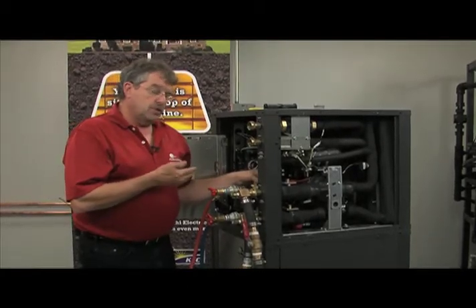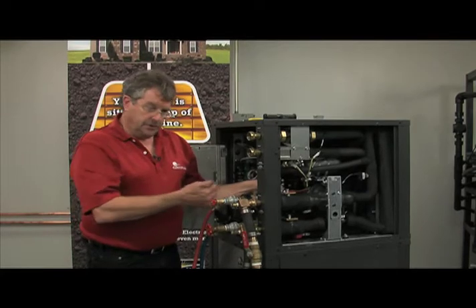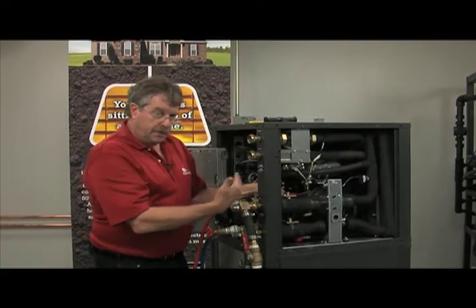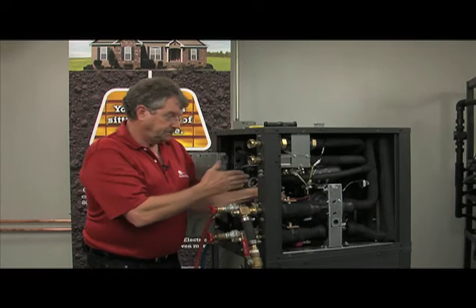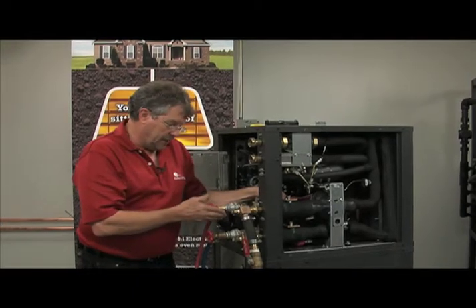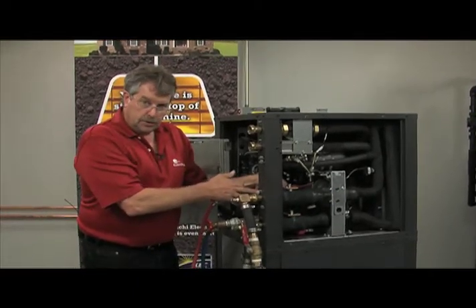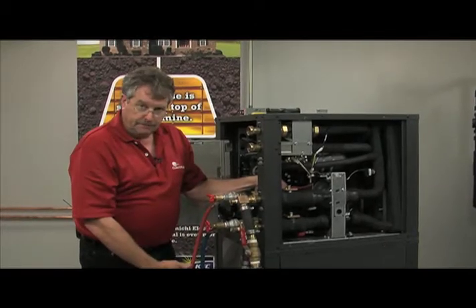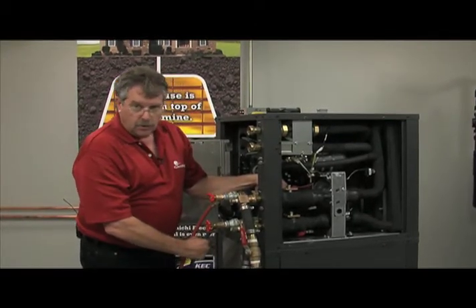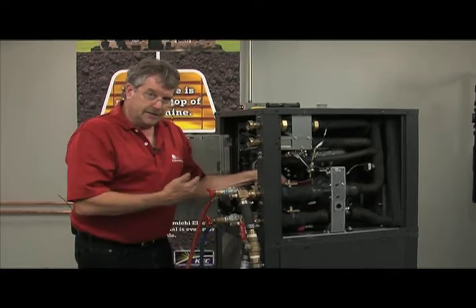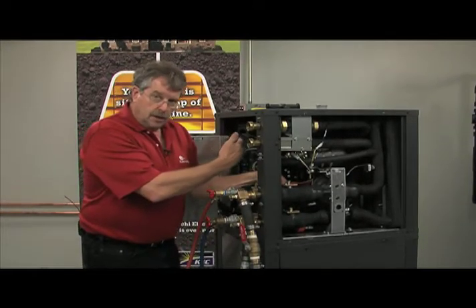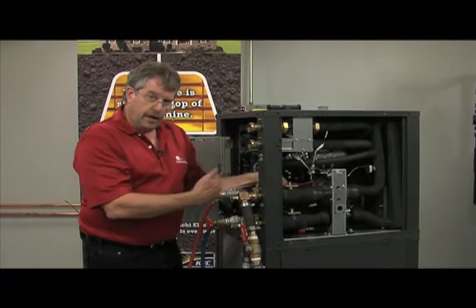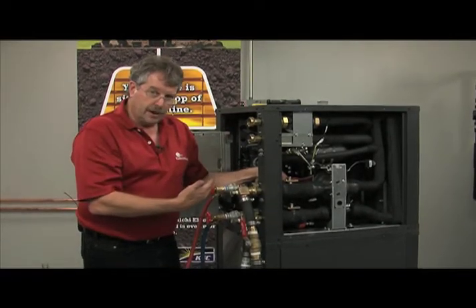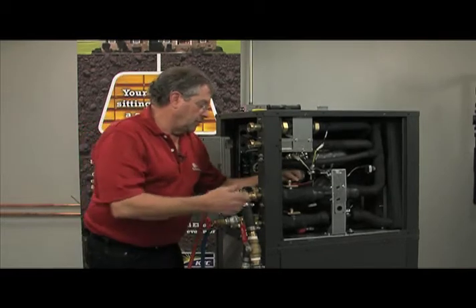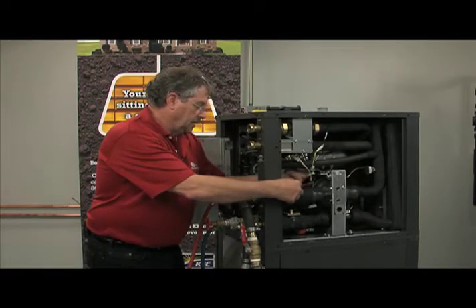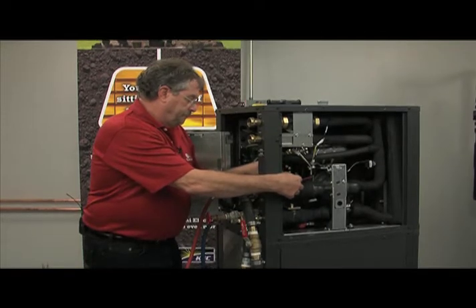Now I'm going to rotate these valves so that I am isolating the ground loop and opening up to our flush ports here, the unit side, and I'm going to take that pressure off on the water out and capture it in a bucket. This hose over here is actually city water pressure, and that's what we're going to use at the end of this segment to just slowly burp the heat pump. We don't have to burp the ground loop because we didn't compromise that, we isolated it. So I'm going to go ahead and orient these valves so that I isolate that ground loop.